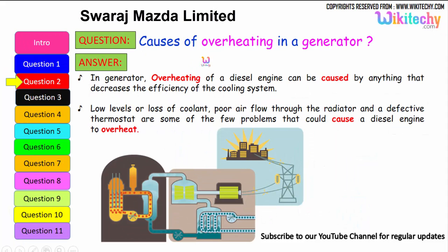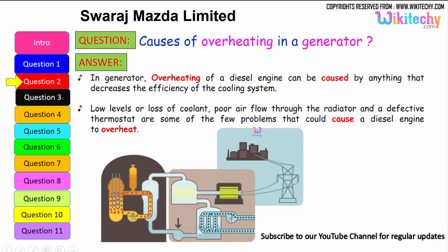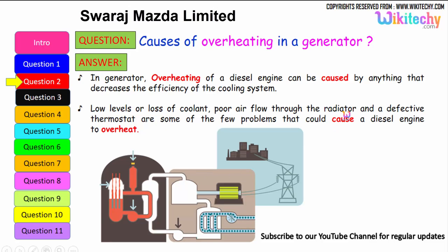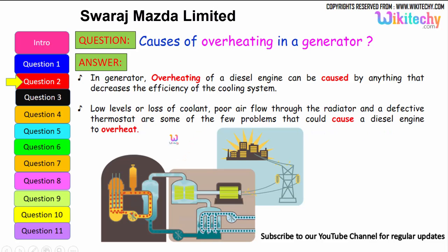Let us move on to the next question: causes of overheating in a generator. Overheating of a diesel engine can be caused by anything that decreases the efficiency of the cooling system. It can be due to loss of coolant, low levels of coolant, poor air flow through the radiators, or a defective thermostat — these are some of the problems that could cause a diesel engine or generator to overheat.